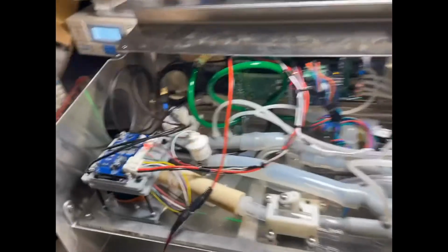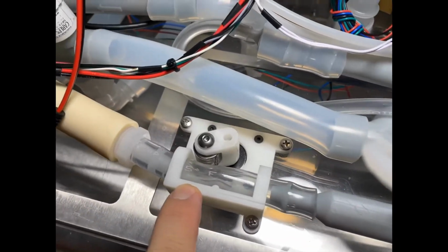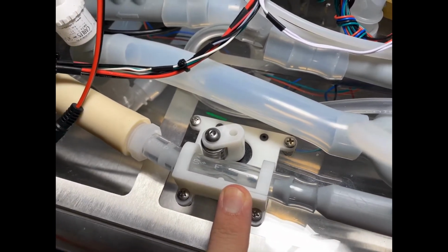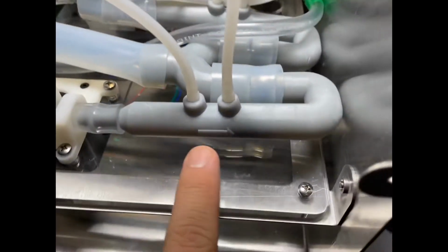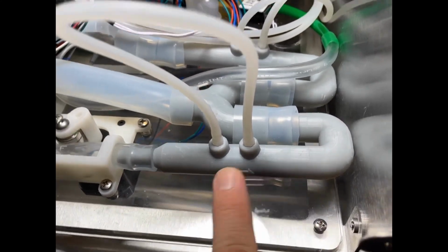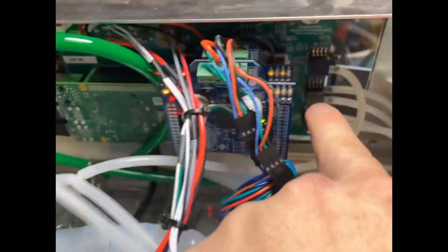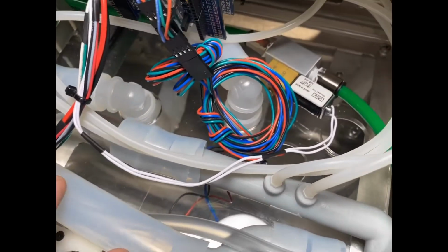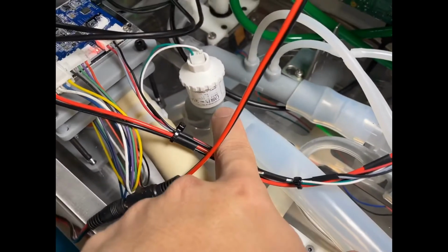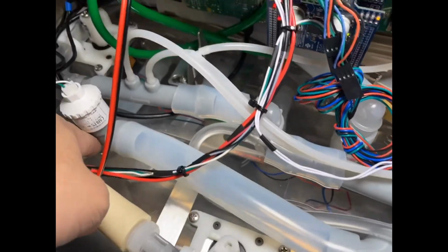All right, so in here we have the blower, which is doing ambient air intake, which then goes to our custom designed stepper motor based pinch valve, which gives us a fast response rate and a low pressure drop across the valve. We have our custom designed and 3D printed Venturi sensors, which is how we do flow. That gets translated into a differential pressure, which goes into our custom designed circuit board, where it is measured as flow. So we continue along this path to the outlet path to the delivered oxygen sensor, and this leads out to what is now connected to the quick lung.